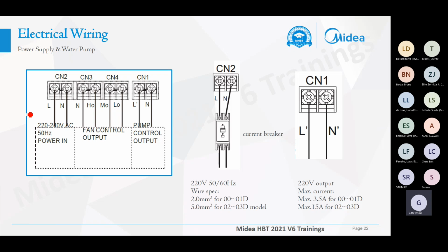For the power supply and the water pump, the wiring connections. Normally, for the power supply, we connect to the LN, CN2 LNs. And for the fan control, it is for the single fan. For the single fan, we can connect to the HML to have the high speed, the middle fan or the low fan, with the three fan speeds. And the pump we connect to CN1.